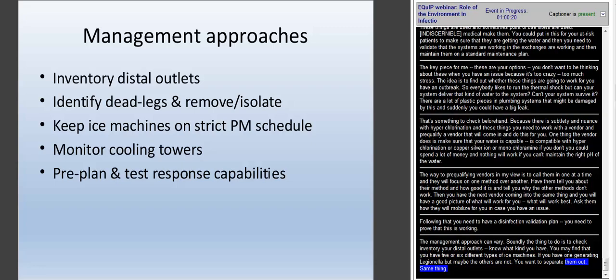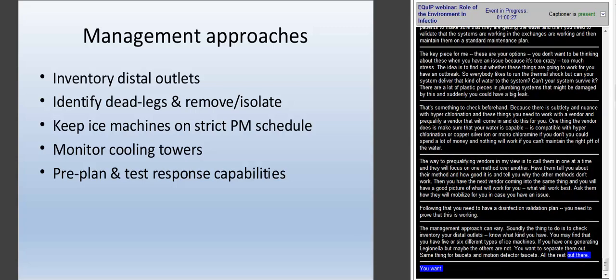You also want to identify your dead legs and either remove them, cap them off, or isolate them. You don't want them connected to your system, because they're important sources of biofilm and Legionella. You also want to keep your ice machines on a very strict PM schedule.